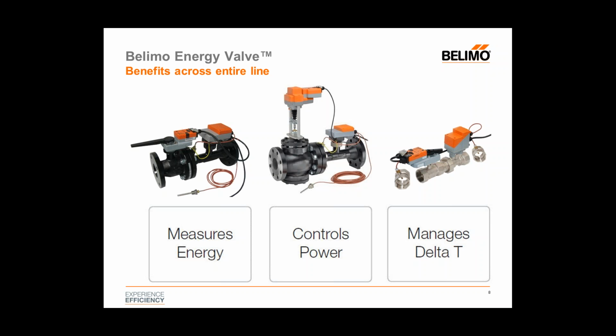Another thing that we talked about earlier was Delta T Manager. What the Delta T Manager does is it looks at the difference between the supply and return water temperatures and compares that to the delta T set point, which is typically the design delta T. An example we used prior was a 10-degree delta T. So it would look and understand where the delta T is in relation to where it wants to be controlled.